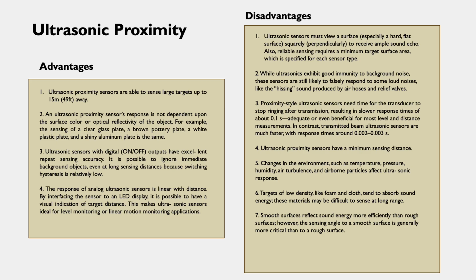One of the disadvantages of ultrasonic proximity: number one, the ultrasonic sensor must view a surface, especially a hard flat surface, squarely to receive ample sound echo. Reliable sensing also requires a minimum target surface area specified for each sensor type. So as with the advantage mentioned, it must be perpendicular - you can't slant it by 10 degrees like shown in the earlier slide, or it won't work properly with ultrasonic proximity.